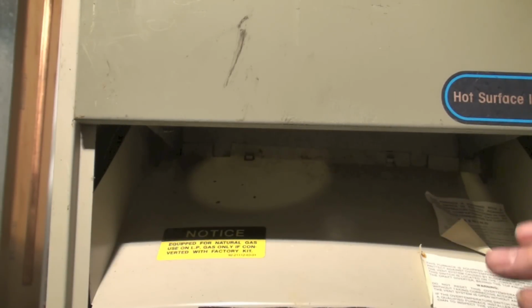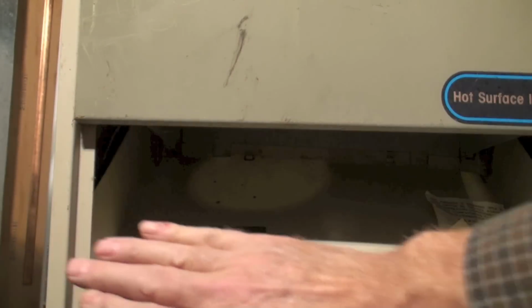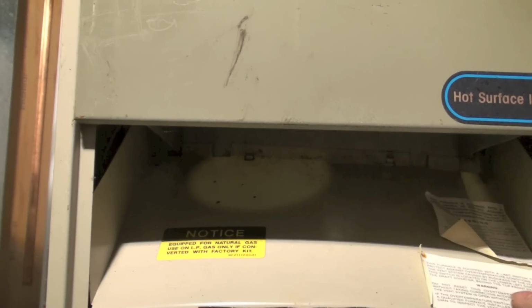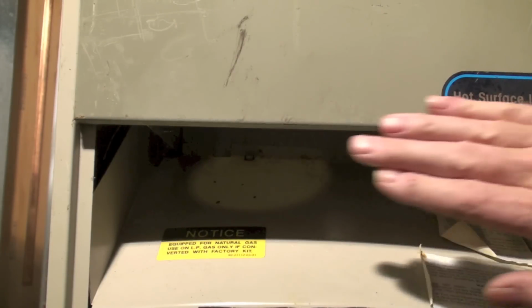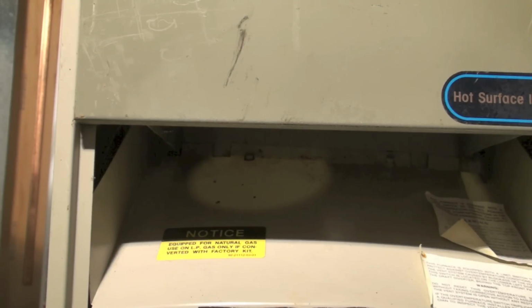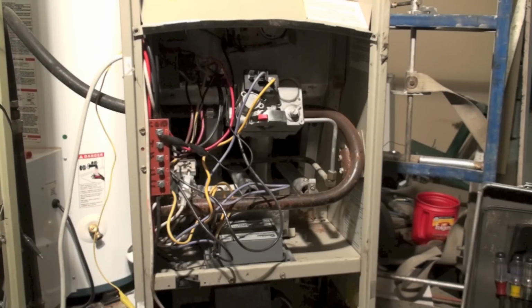Okay, once that's lit off after that switch was reset, remember, if a switch like that is reset, it means that there's a problem. So run your hand across here and then run it down here. You can also take a match or a lighter and go anywhere around here. The flame should always draw in. If it's hot here or it pulls out, then you've got a venting problem. So you need to find out what the venting problem was. Okay, we're going to continue on with troubleshooting no heat in the next one, and it's going to be on the ignition control and problems with the ignition control.